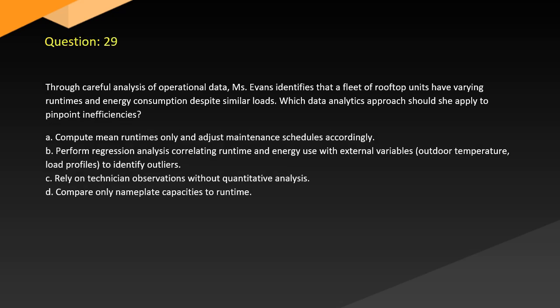Question 29. Through careful analysis of operational data, Evans identifies that a fleet of rooftop units have varying runtimes and energy consumption despite similar loads. Which data analytics approach should she apply to pinpoint inefficiencies? A. Compute mean runtimes only and adjust maintenance schedules accordingly. B. Perform regression analysis correlating runtime and energy use with external variables, outdoor temperature, load profiles, to identify outliers. C. Rely on technician observations without quantitative analysis. D. Compare only nameplate capacities to runtime.